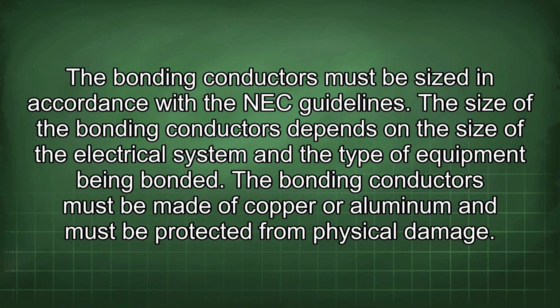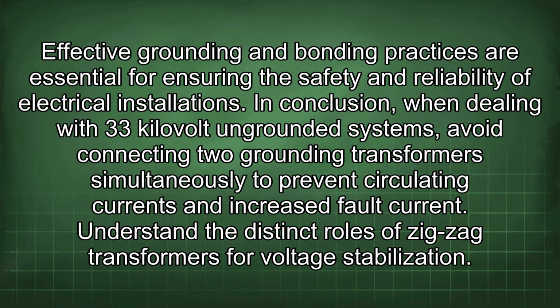The bonding conductors must be sized in accordance with the NEC guidelines. The size of the bonding conductors depends on the size of the electrical system and the type of equipment being bonded. The bonding conductors must be made of copper or aluminum and must be protected from physical damage. Effective grounding and bonding practices are essential for ensuring the safety and reliability of electrical installations.